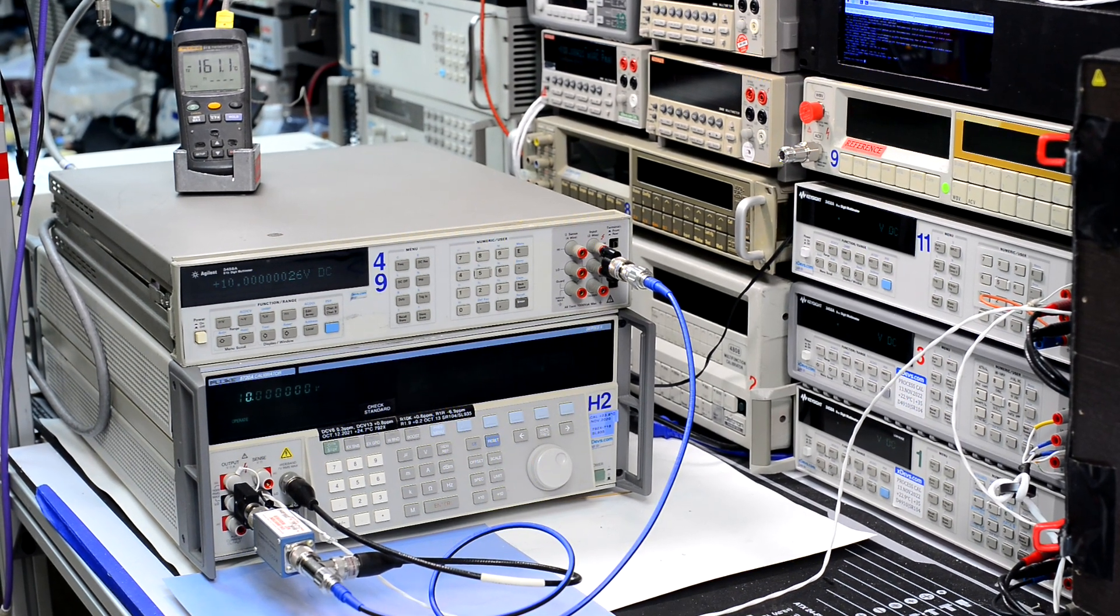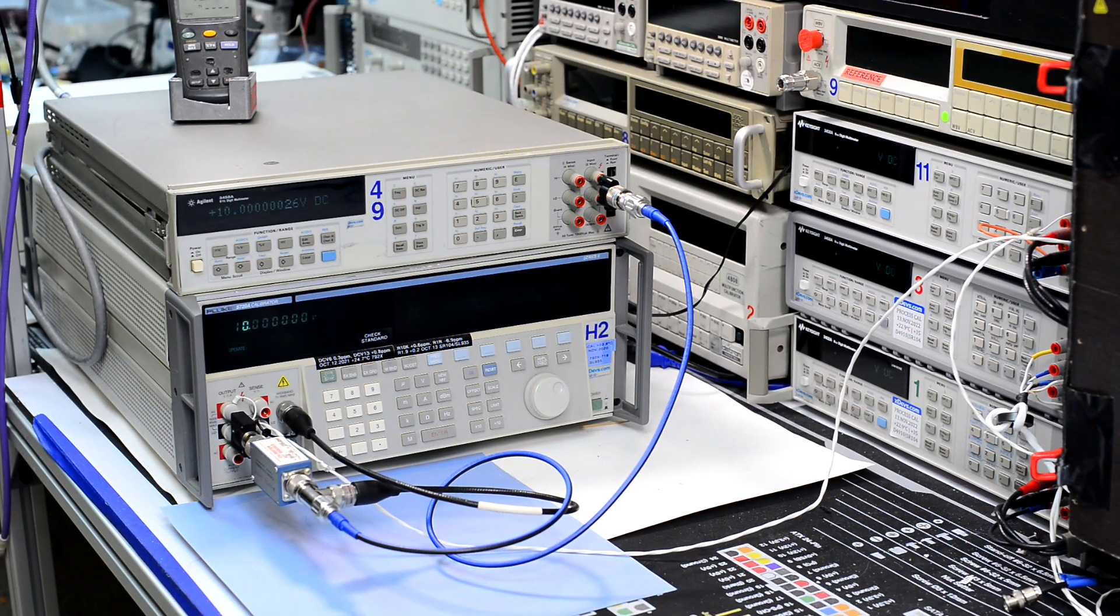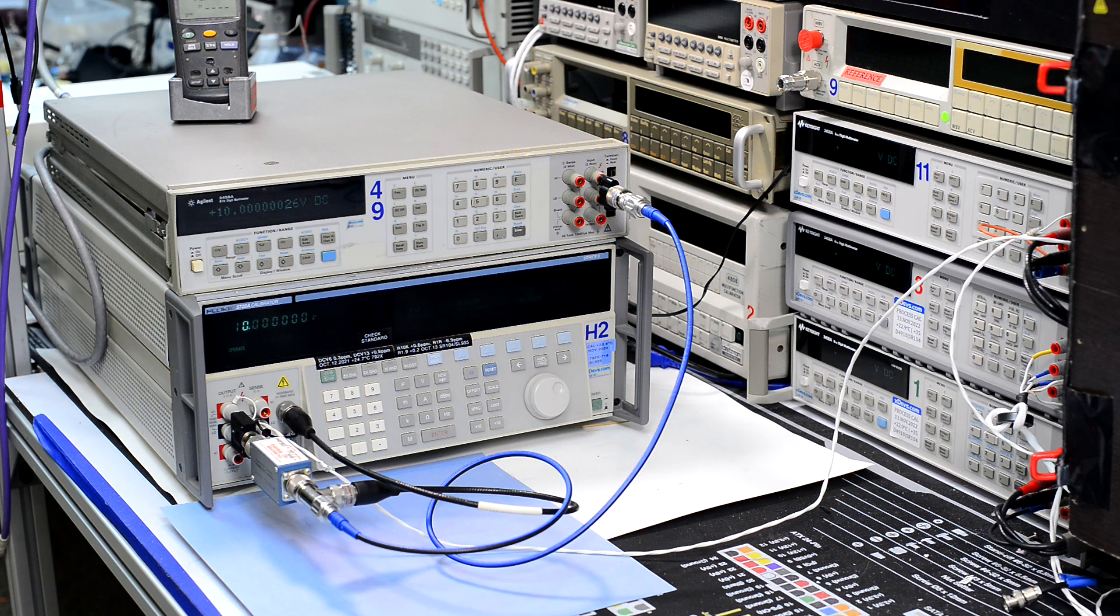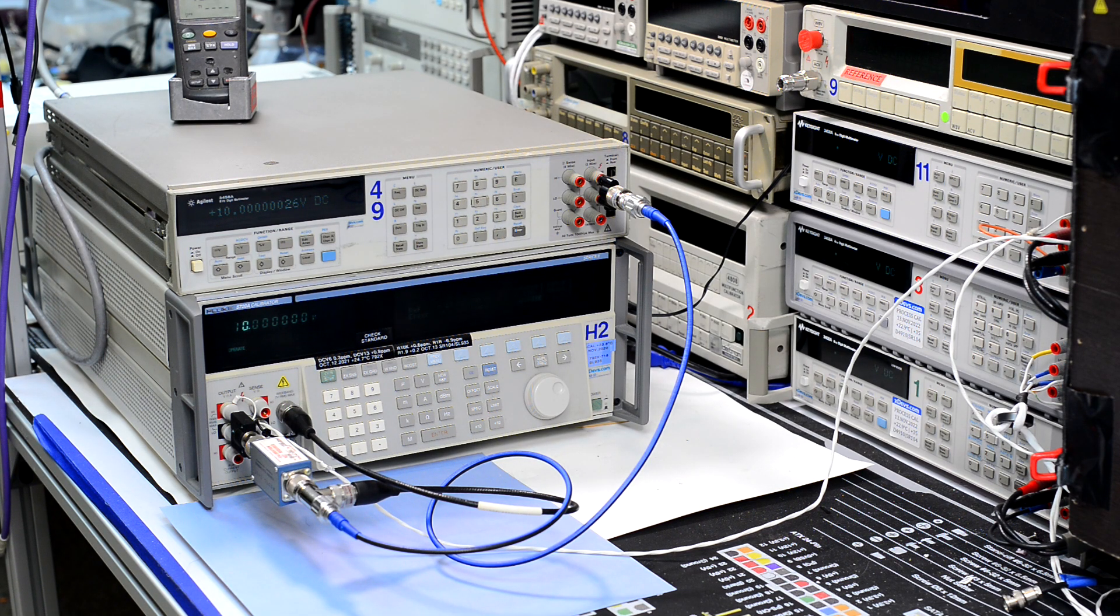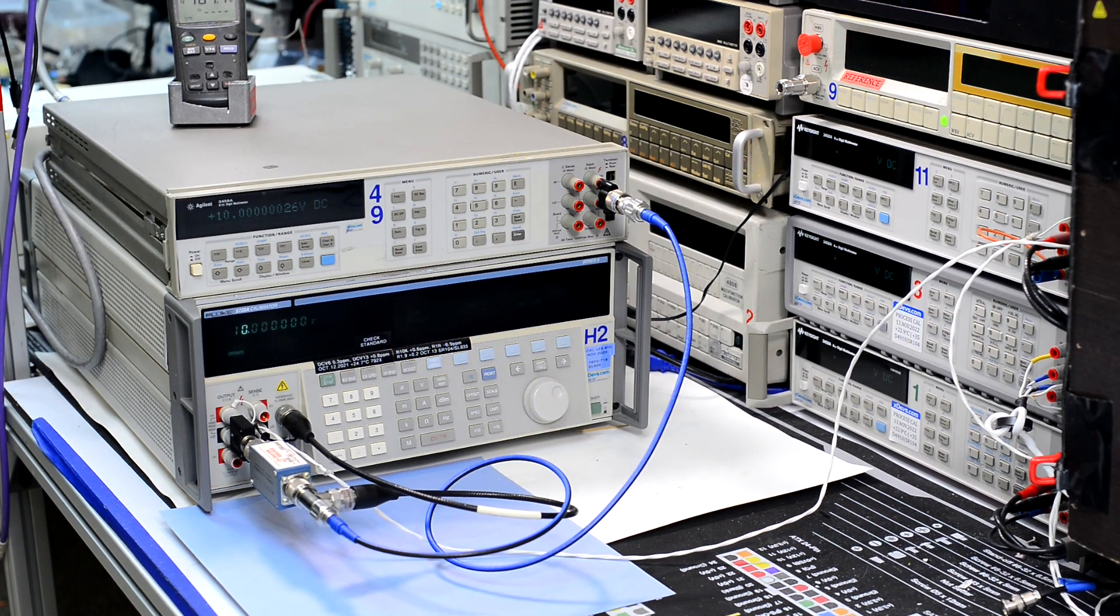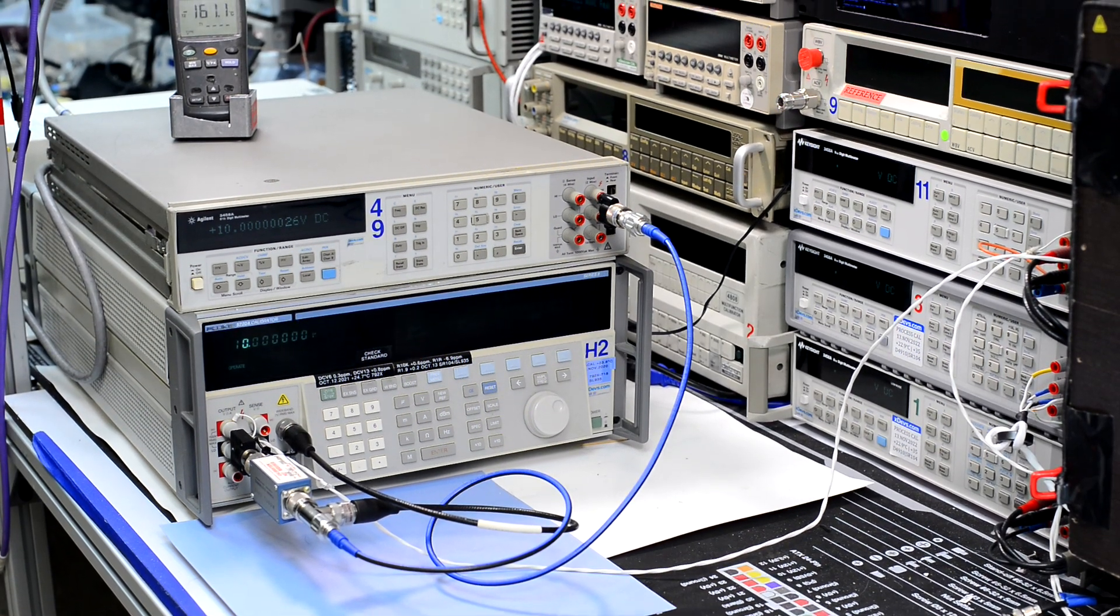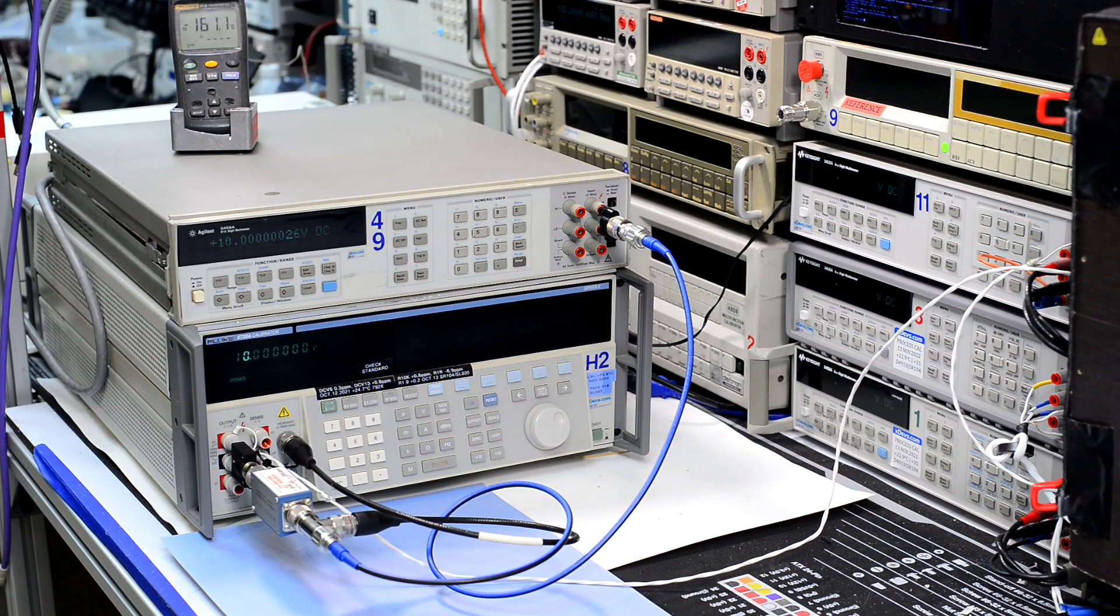And there is a special 6-wire connection between the calibrator and DMM, because the calibrator is quite noisy by itself, so we need to filter out some noise to utilize extra resolution on DMM.